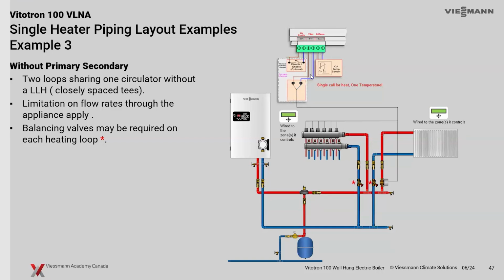Thermostats wired to their zones as typical to the 24-volt side. One common call. So all of our zone valves, our Telestats, are all wired back to the main end switch contact on the boiler control. Of course, regardless of what emitter here is calling, the boiler is going to accept that set point and fire to whatever we're looking for there. And just a note, when you're piping like this with zones instead of pumps, you may need to have some sort of flow setters to balance the flow rates required on the system.